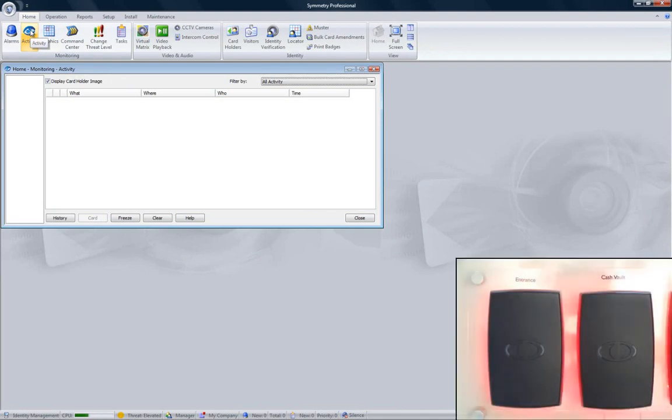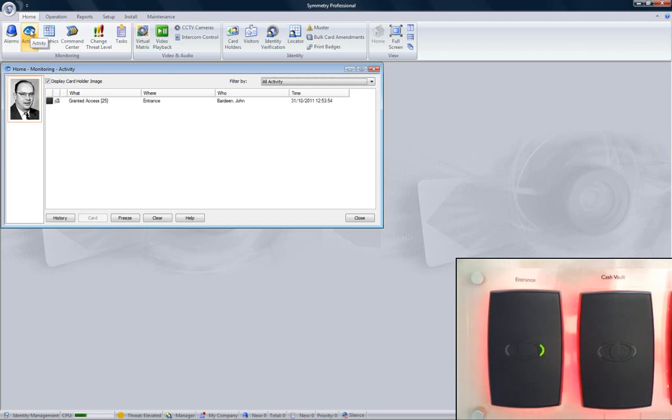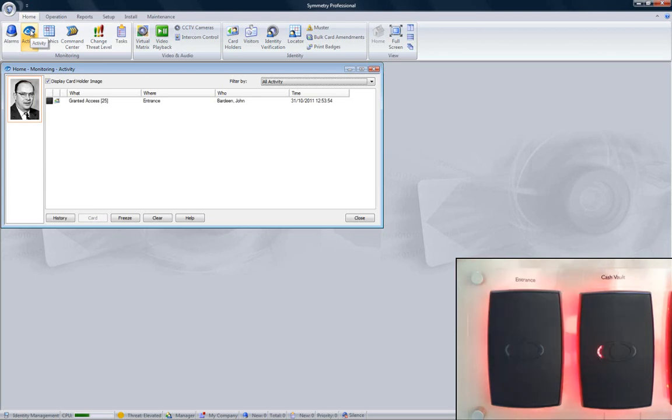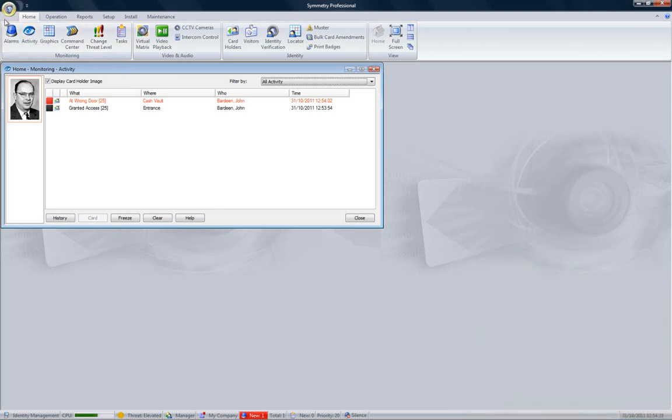To see activity on the system, click the Home tab, followed by the Activity icon. Each card reader has a green and red LED to indicate whether the card has been accepted or rejected. When a valid card is presented to the Entrance card reader, it is accepted, the activity is shown on the screen, and the green LED comes on. When the same card is presented to the Cash Vault reader, it's rejected, activity is shown in red, and the red light comes on.